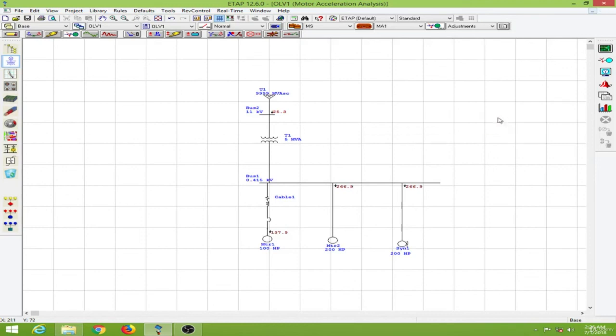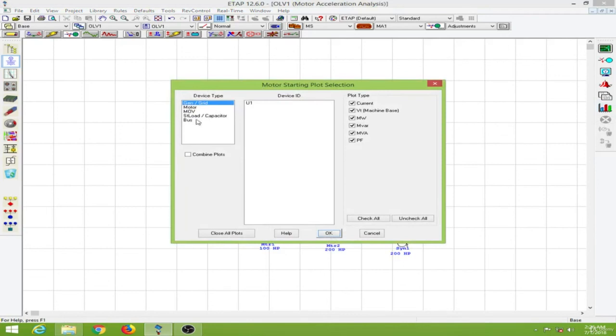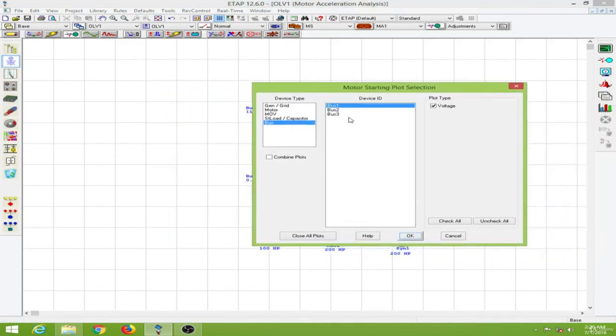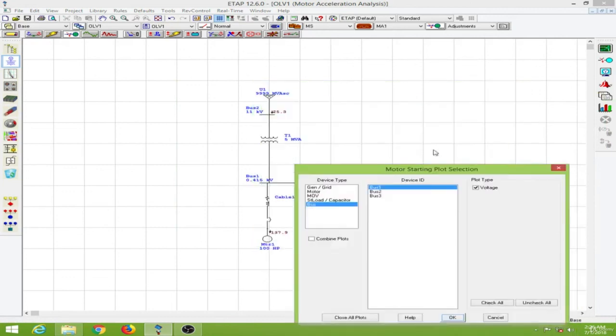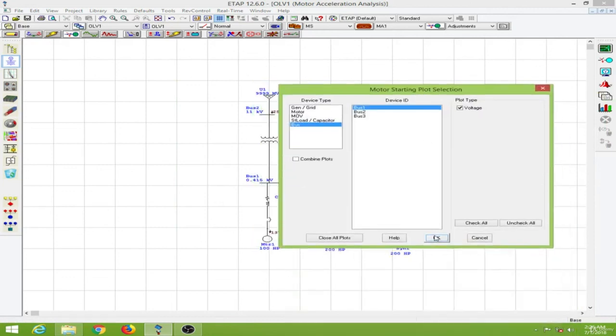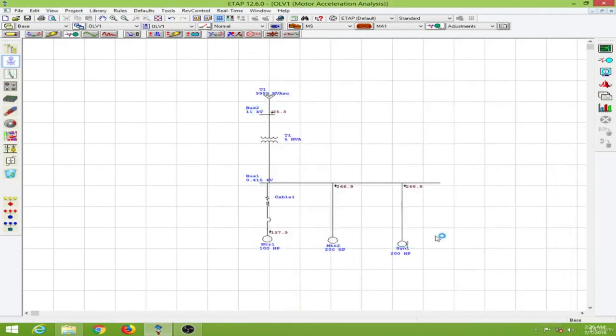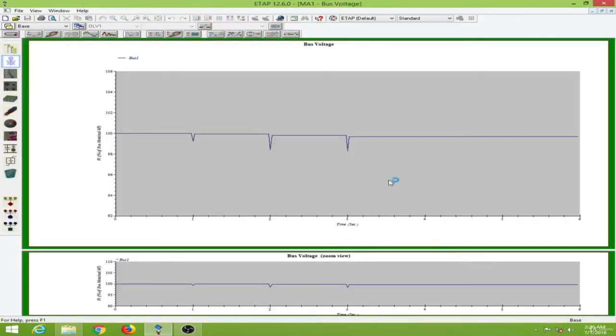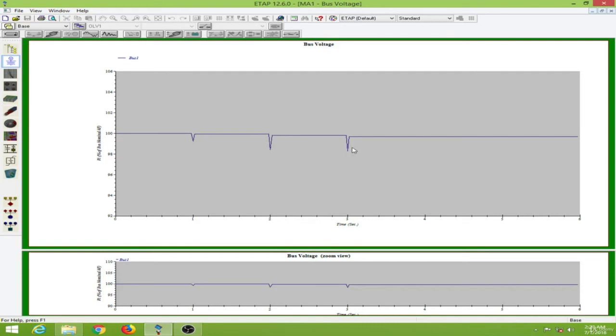So let us observe some of the bus voltages over here. So we will look at the bus 1 voltage over here. Now as you can see in the first second we have a drop in voltage over here owing to starting the motor 1. And the voltage drop here is more because this time we are starting a 200 HP motor over here. And at the time 3 seconds again we have started this synchronous motor over here. So this is the voltage profile during the starting of these 3 motors over here.